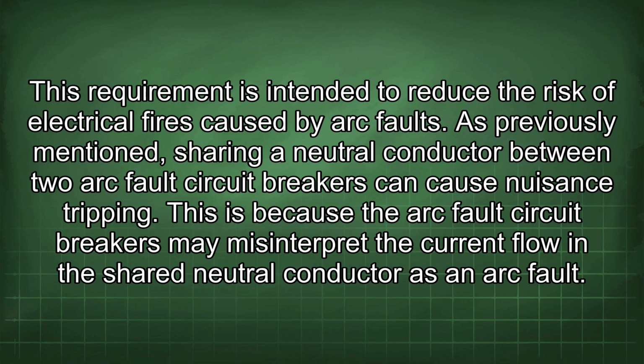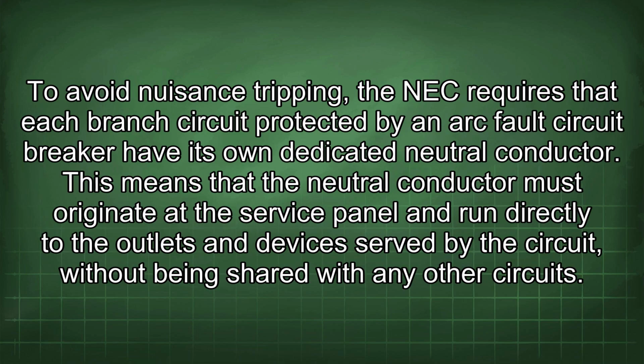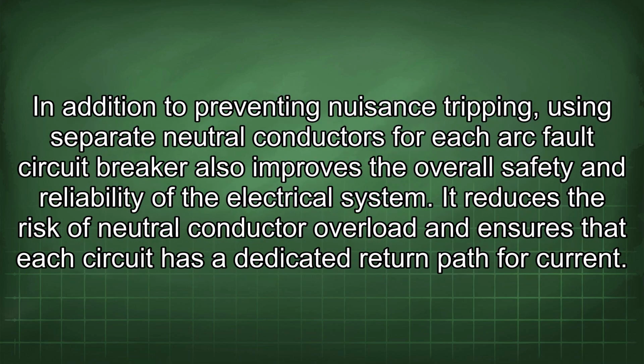As previously mentioned, sharing a neutral conductor between two arc fault circuit breakers can cause nuisance tripping. This is because the arc fault circuit breakers may misinterpret the current flow in the shared neutral conductor as an arc fault. To avoid nuisance tripping, the NEC requires that each branch circuit protected by an arc fault circuit breaker have its own dedicated neutral conductor. This means that the neutral conductor must originate at the service panel and run directly to the outlets and devices served by the circuit without being shared with any other circuits. In addition to preventing nuisance tripping, using separate neutral conductors for each arc fault circuit breaker also improves the overall safety and reliability of the electrical system.